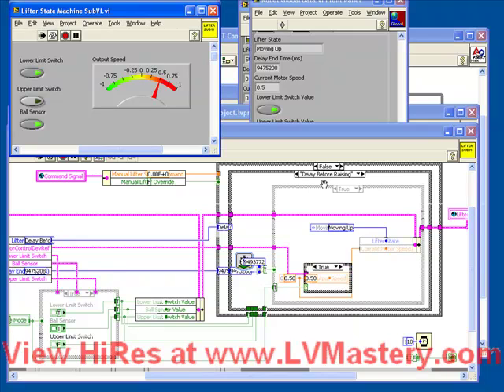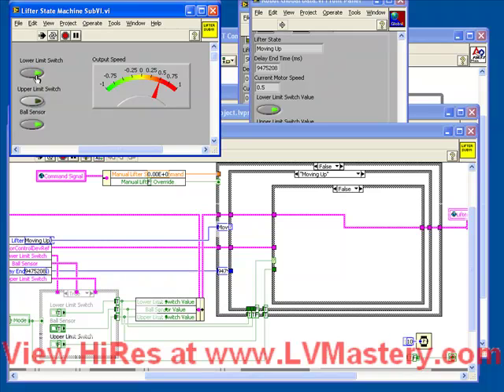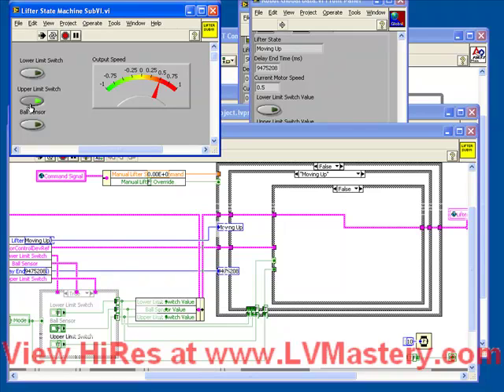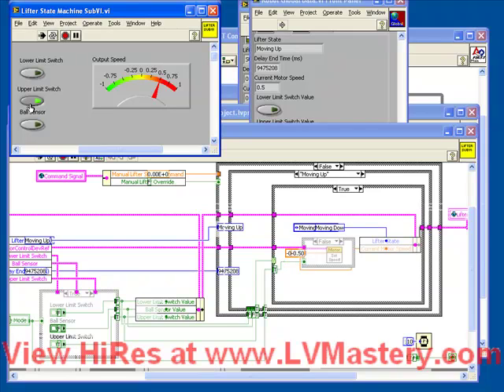Our speed is set to positive 0.5. Our state is moved to Moving Up. Now we're in the Moving Up state. One of the tricks to this kind of simulation is keeping track of the digital inputs that you're simulating. Now that we've started moving up, if I'm going to properly simulate, I should probably turn off the lower limit switch and turn off the Ball sensor. It's important to do that — otherwise when you're testing, you'll find that you're cycling over and over again, because in real life these switches will turn off. So we're moving up and waiting for the upper limit switch. If we trigger the upper limit switch, we see our speed is set to minus 0.5, we're moving down again, and the whole loop has restarted.